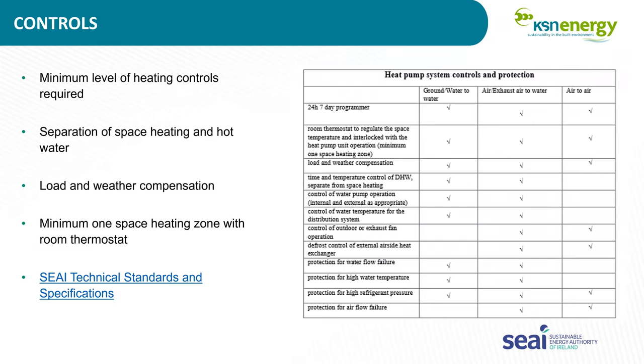With regards to the controls, there's a minimum level of controls required, again, this is all for the SEAI grant side of things. You must have separation of space and hot water heating. There has to be load and weather compensation. And as a minimum, there needs to be one space heating zone with a room thermostat or at least a sensor to measure the temperature. That table there shows a bit more detail on what controls are needed for the various types of heat pumps available on the market: air to water, ground source, exhaust air, air to air. In the link there in blue, SEAI's technical standards and specifications, if anyone wants to look into it further, that link will take them to the download page where you can look at the section for heat pumps.